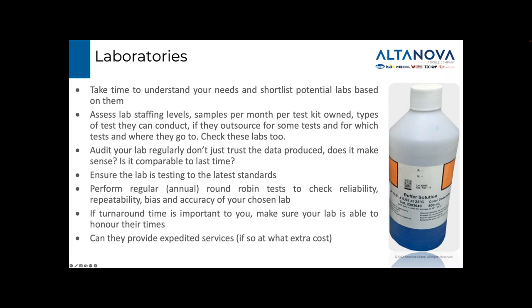The picture on the right shows a buffer solution for acidity tests that I found in a lab during an audit. It was 5 years out of date at the time of the audit. Doble can help you assess your laboratory to check if the data is representative through the use of round-robin testing, calibration standards, or on-site laboratory auditing.